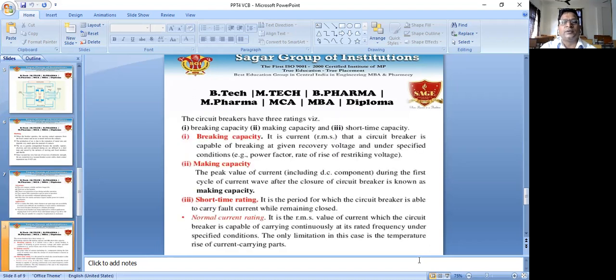Okay, and this is the circuit breaker having three ratings: breaking capacity, making capacity, and short time capacity. Breaking capacity is the RMS current that the circuit breaker is capable of breaking at a given recovery voltage and under specified conditions. Making capacity: the peak value of current, including DC components, during the first cycle of the current wave after the closure of the circuit breaker is known as the making capacity. Short time rating is the period for which the circuit breaker is able to carry fault current while remaining closed.